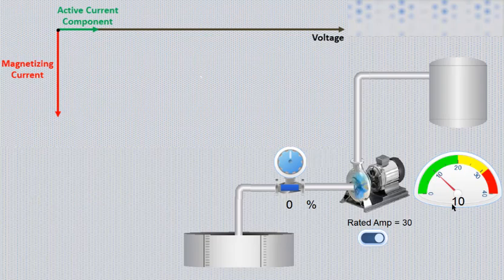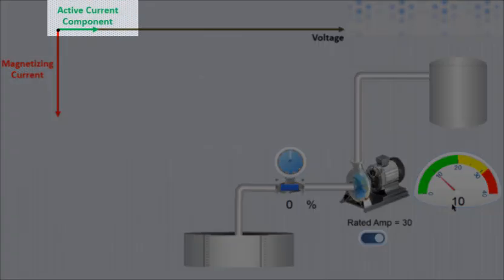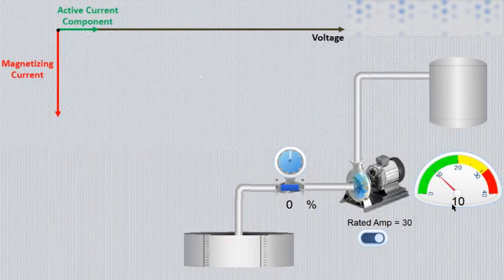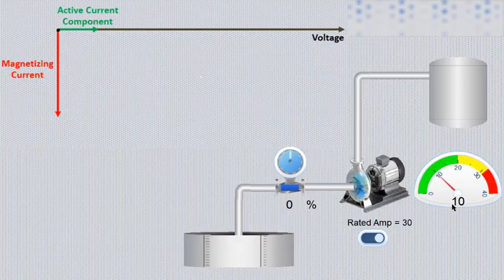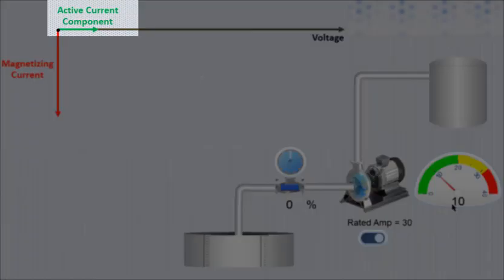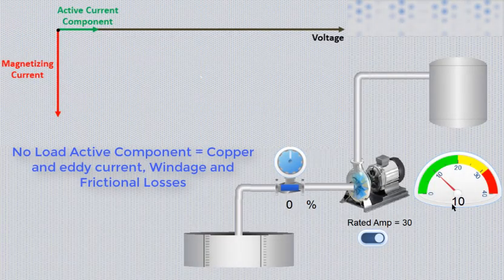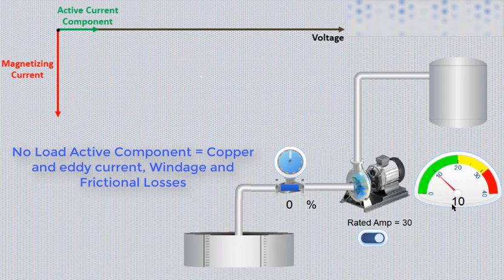Normally no load current consists of magnetizing current and active component of current. Active component is in phase to voltage, while magnetizing component lags 90 degree behind voltages. No load active component comprises copper and eddy current, plus windage and frictional losses. This component is normally less than magnetizing current, which is reactive component of current.